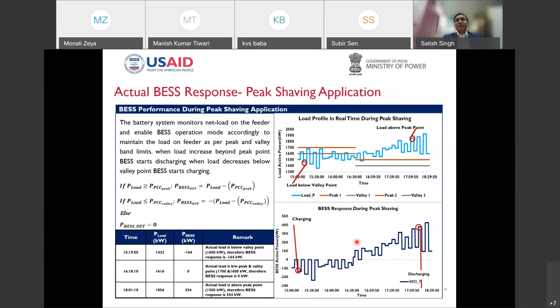This is charging. Similarly, from 1630 to say 1830, if my peak band limits are between 1400 and 1500, the battery would respond accordingly so as to limit the overall import from the grid. These are the formulas we have designed and tested, and we are trying to showcase that the response is actual. This is an instant response. There is no inherent time delay, and these values have been captured from the actual live system.